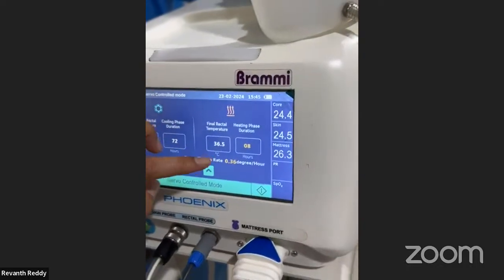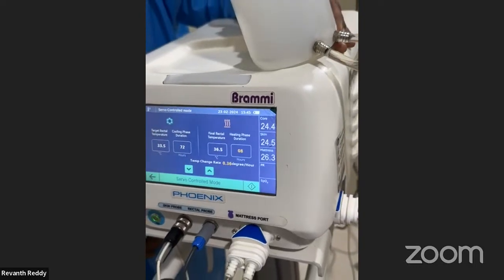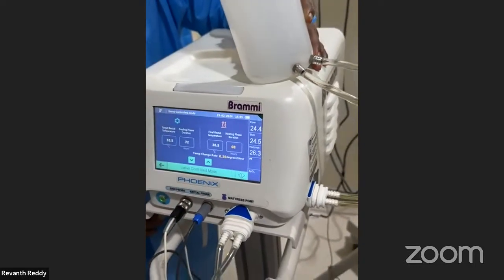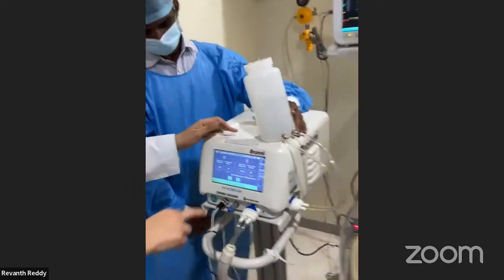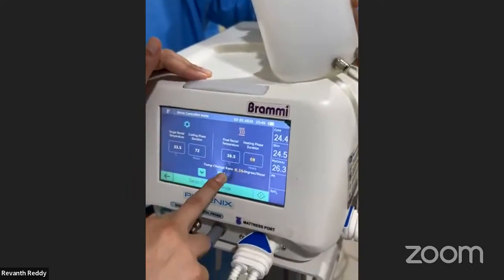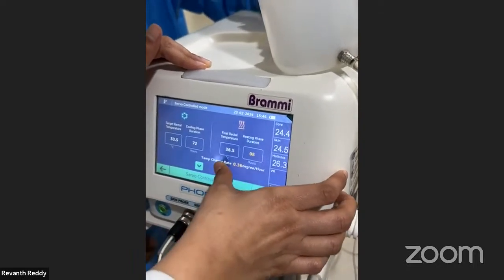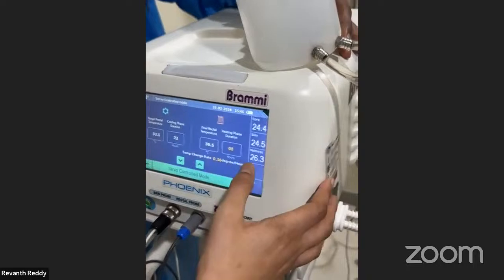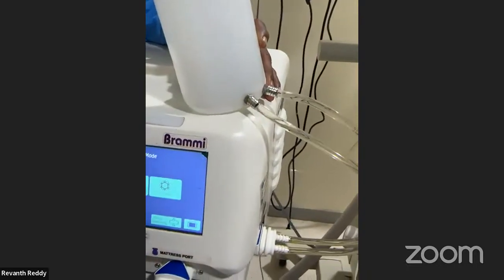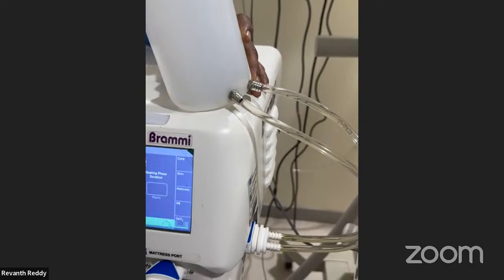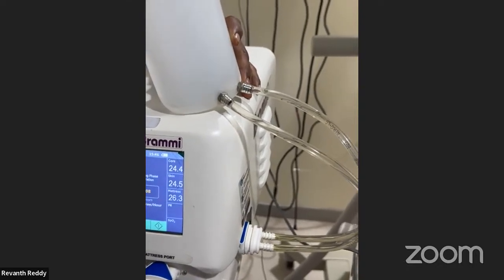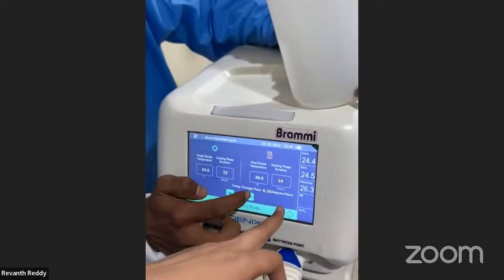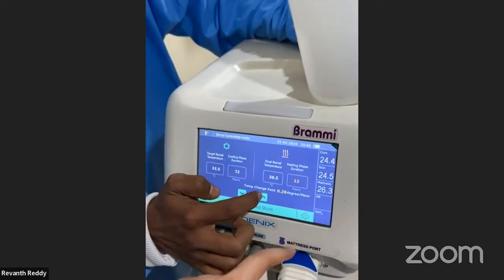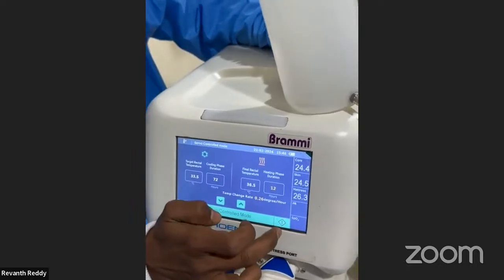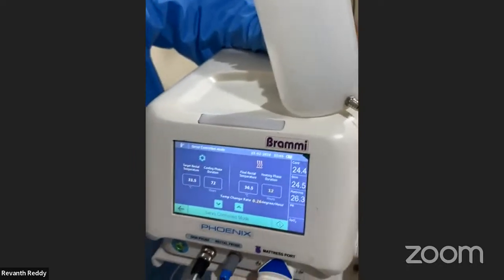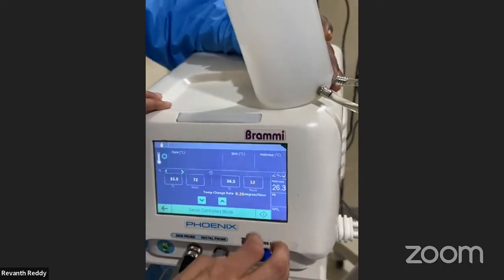So from 33.5 to 36.5, at 0.5 degrees Celsius per hour, we'll need 6 hours. But supposing you want to go more slow and choose say 0.25 degrees Celsius per hour, you will want to possibly keep the duration at maybe 12 hours. So automatically it will show you the duration, the rate of cooling, the rate of rewarming also will keep changing. Yeah. So now we have chosen 12 hours. So once you have chosen all your settings, we are ready to go. So we can go directly to the cooling mode.